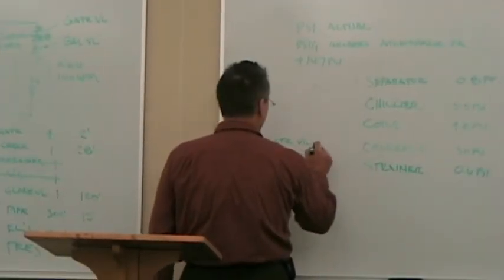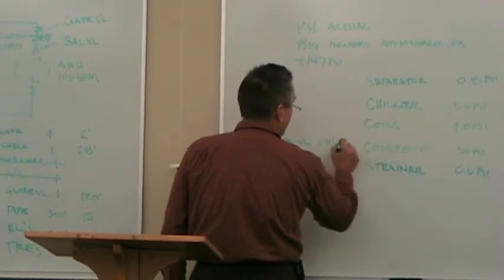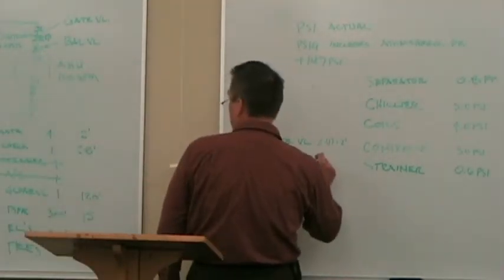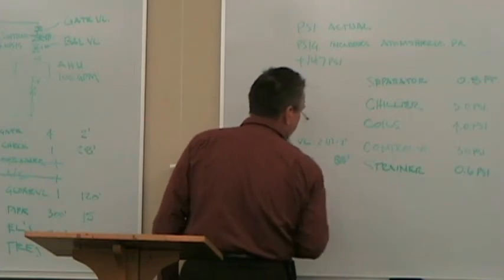So I've got all my piping, now I need to do my 2-inch gate valve. Each gate valve is a little over 1 foot. How many did I have? 2, times 1 is 2 feet equivalent pipe. A balancing valve on 3-inch pipe is 85 feet. And I've got 1, that's 85 feet equivalent pipe.